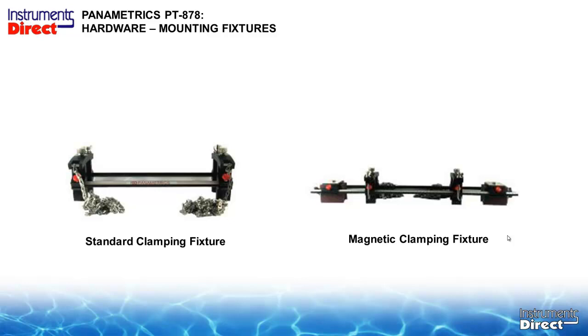For larger applications, if you've got a lot of big magnetic or a lot of big metal pipe applications, the magnetic clamp is a nice tool, but mind you, it is the same standard clamp fixture with another, I don't know, 8 to 12 inches on either side holding the magnet, so it is a big transducer. But if you've got a lot of 24-inch pipes that you're walking around, going pipe to pipe, it'd be a nice tool. It has an optional carrying bag, but do take note that the maximum temperature of the magnets, I believe, is 140 degrees F.